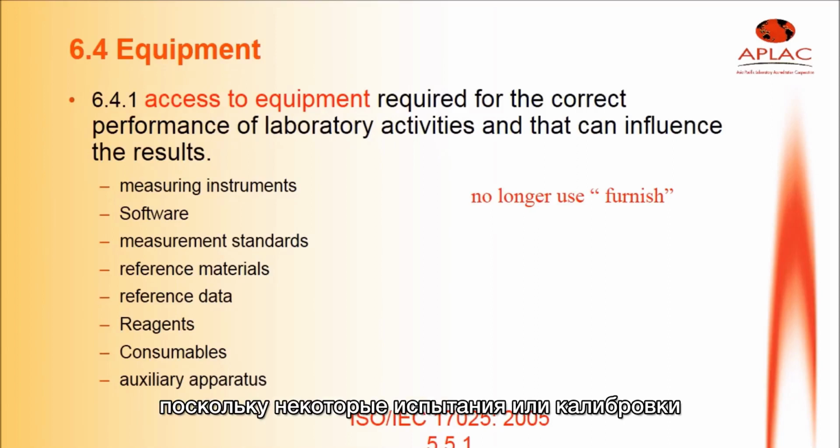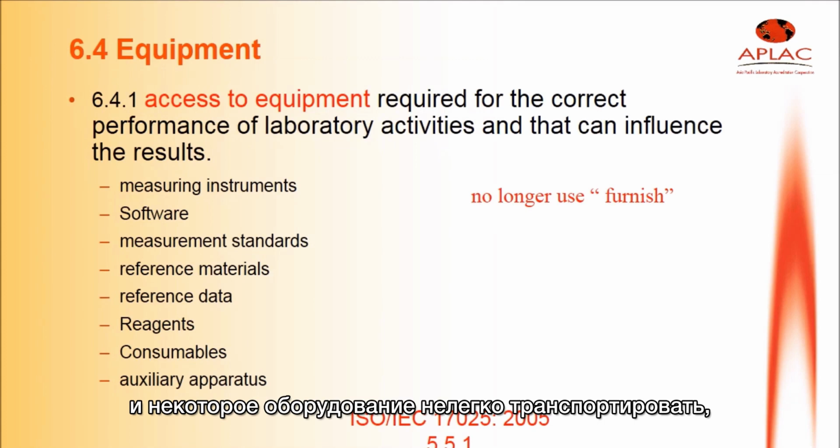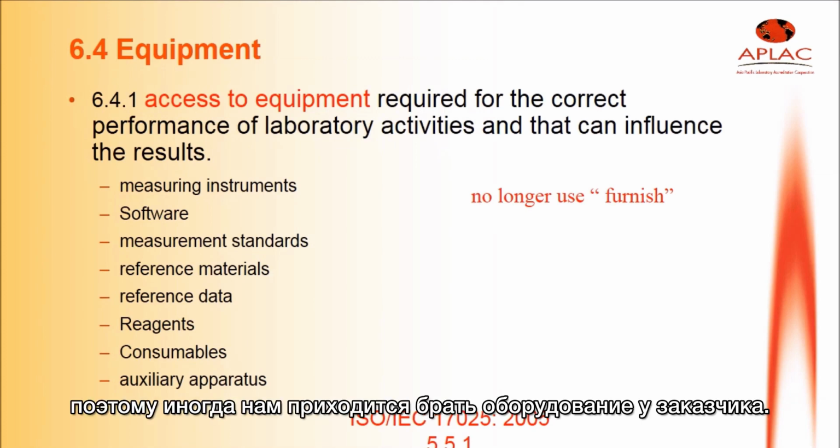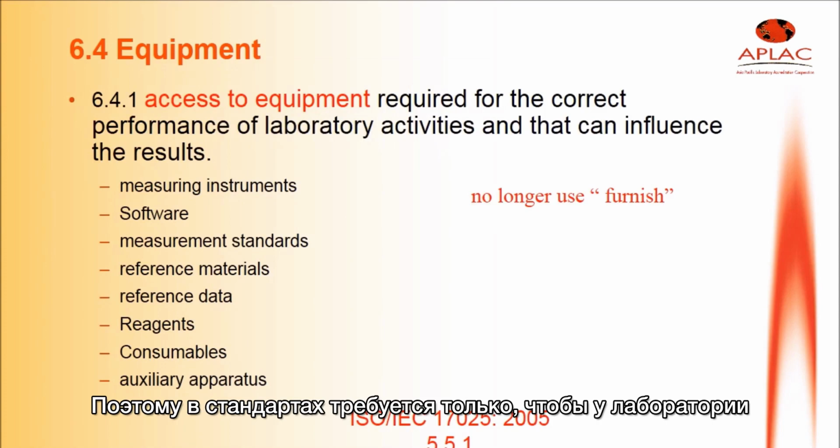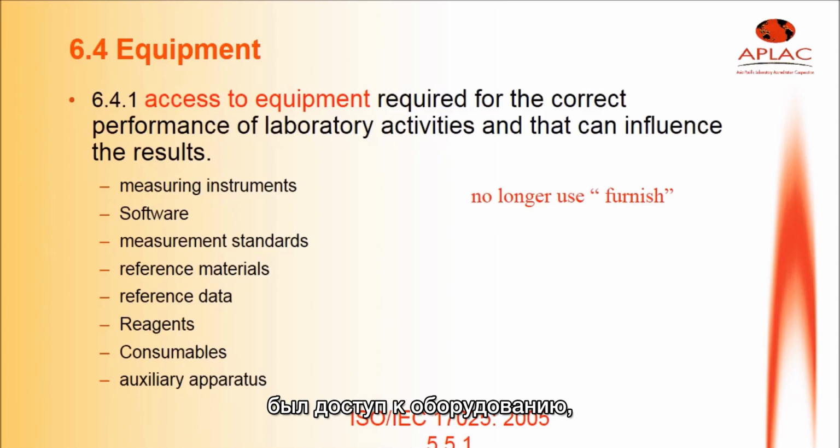Some testing or calibration is conducted at the customer side, and some equipment cannot be transported easily, so sometimes you have to borrow the equipment from the customer. So the standard only requires that the laboratory shall have access to, not furnish, the equipment required.